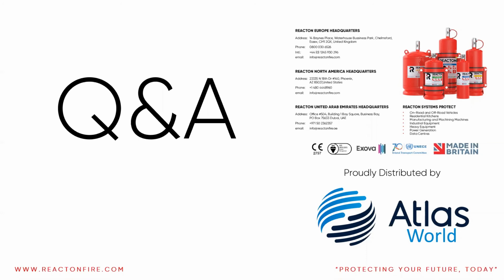We install these systems on buses, and quite often buses go in for retrofit parts and new pipes get added and taken away. So that servicing point is a really nice point for you to just have a look, make sure that you're still protecting what you set out to protect and that nothing else has been changed inside machines. Again, on the static systems, so electrical panels and that kind of thing, it's mainly a visual inspection, just checking the detection tube, checking that there's no wear and tear around it, or any sort of third-party contamination. Incredibly simple to service, but it must be done by a trained professional because these are pressurized vessels.